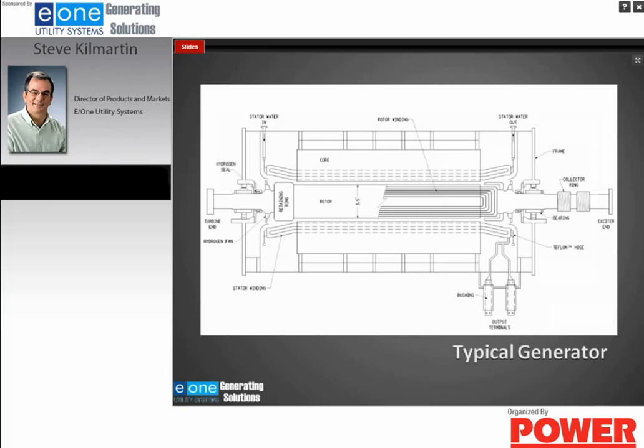You will note on the left-hand side a hydrogen seal. And this seal is what keeps the hydrogen from escaping from the generator. This seal is on the turbine end of the generator. There is another seal on the exciter end of the generator. Also, you can note in this that there's a hydrogen fan on the left-hand side of the generator as well as on the right-hand side of the generator. Some generators have one fan, some of them have two. Another place for hydrogen to escape is any penetration in the generator, such as the bushings and lower leads, any manhole covers. Those are potential for hydrogen leak, although the biggest potential for a hydrogen leak is on the seals in the rotor.